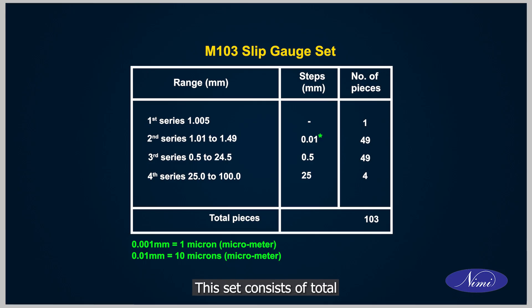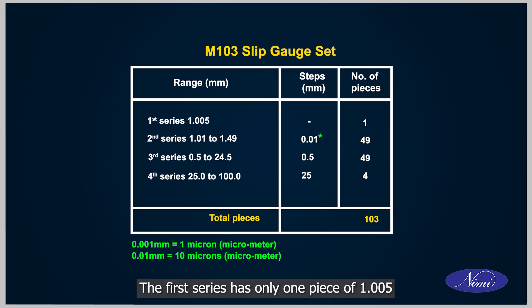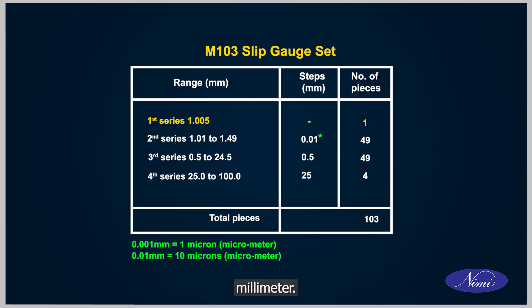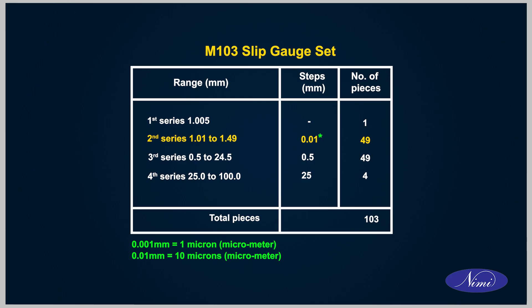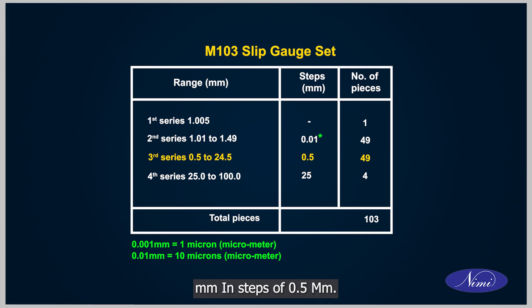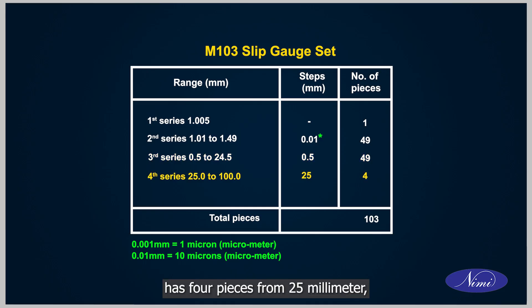M103: This set consists of a total of 103 pieces in 4 series. The first series has only one piece of 1.005 mm. The second series has 49 pieces from 1.01 to 1.49 mm in steps of 10 microns. The third series has 49 pieces from 0.5 mm in steps of 0.5 mm. The fourth series has 4 pieces from 25 mm to 100 mm in steps of 25 mm.